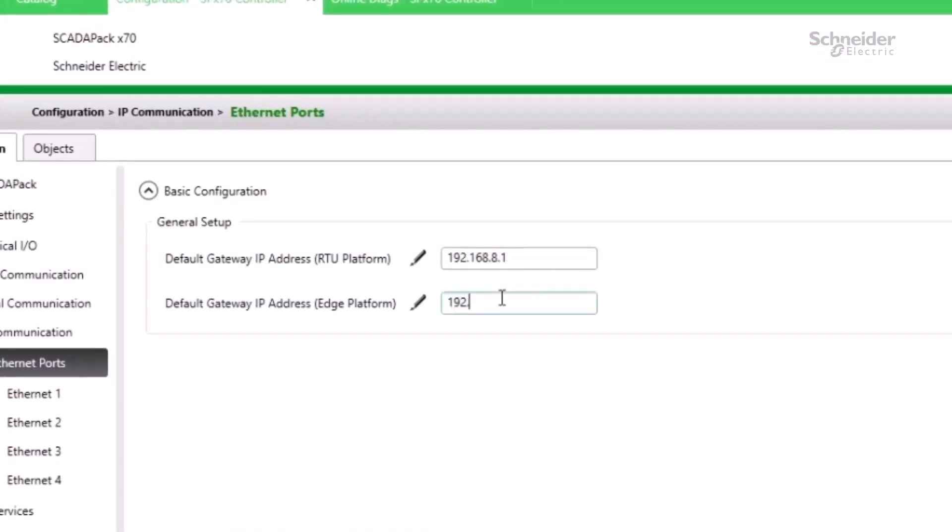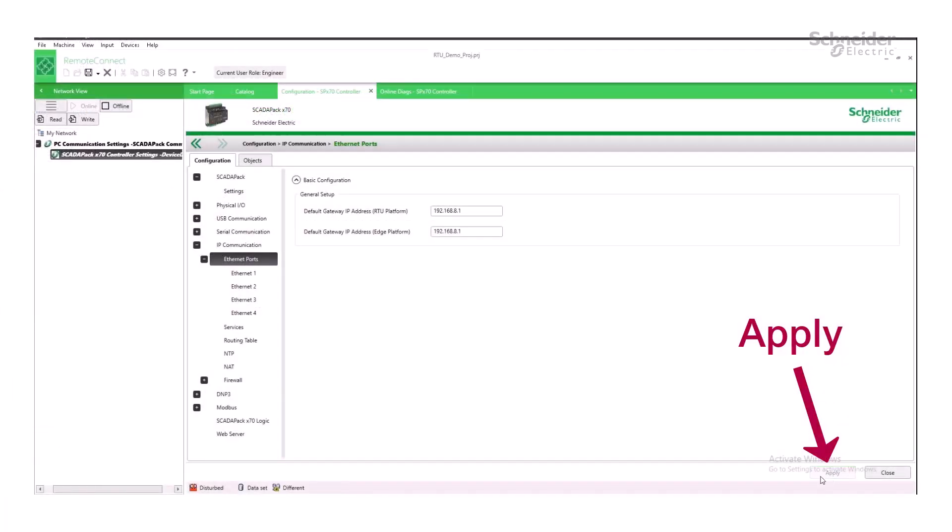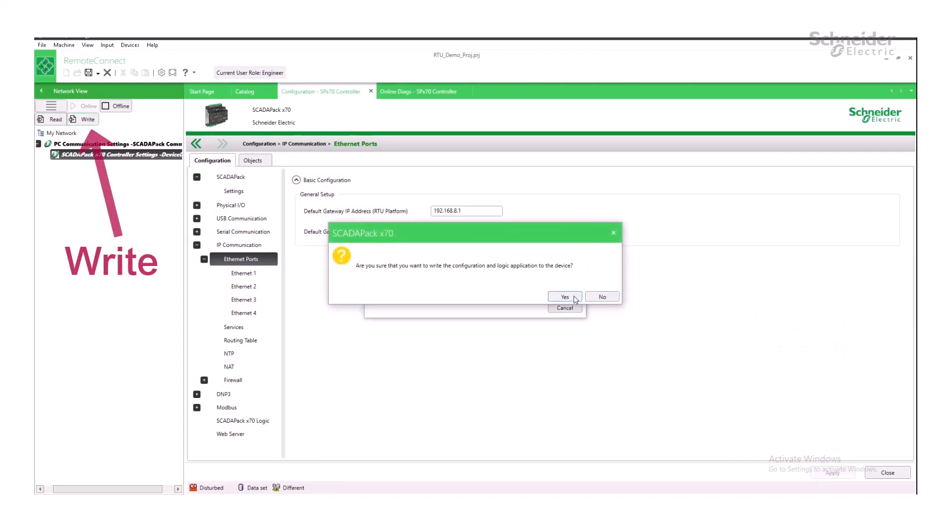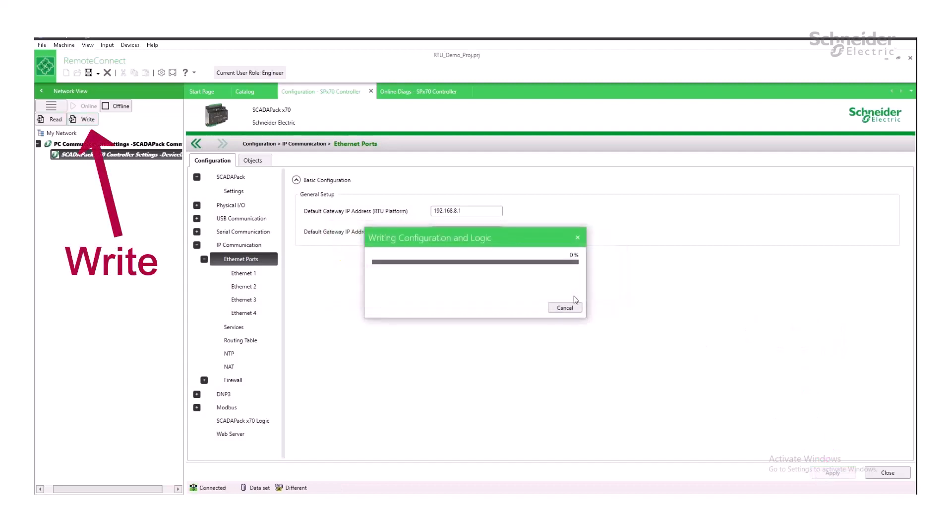You then configure the SCADAPack's gateway to point to your router's IP address. This means that if your router is at 192.168.8.1, that's what you put as your SCADAPack's gateway. After clicking Apply for the network settings and going online, click Write to push these network settings to your SCADAPAK.